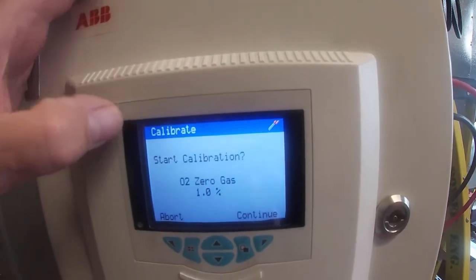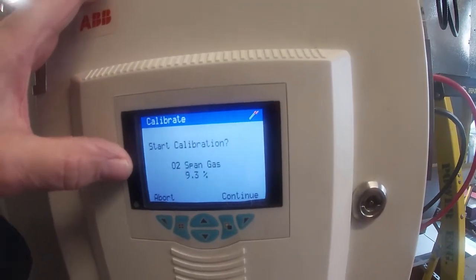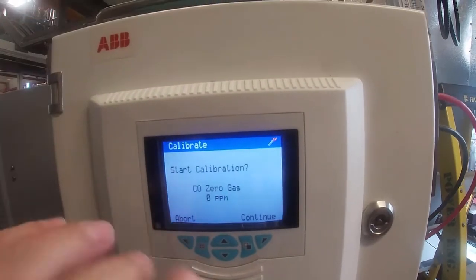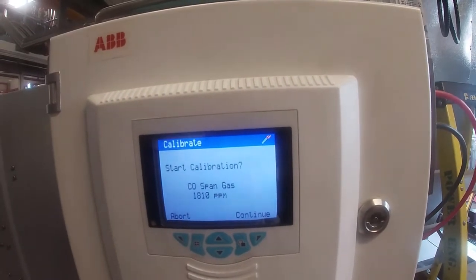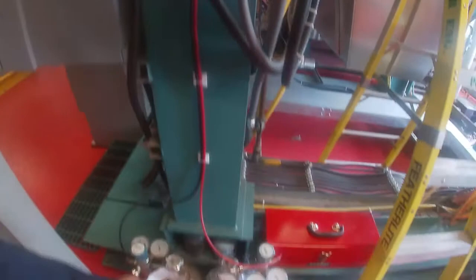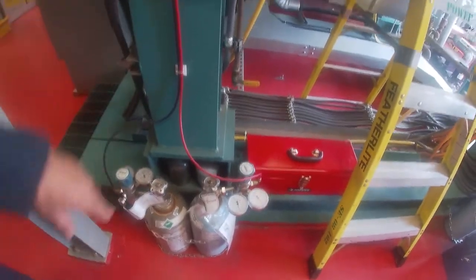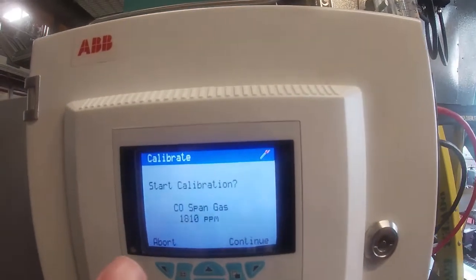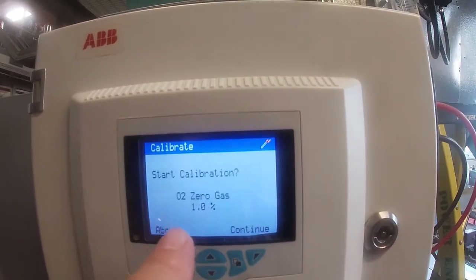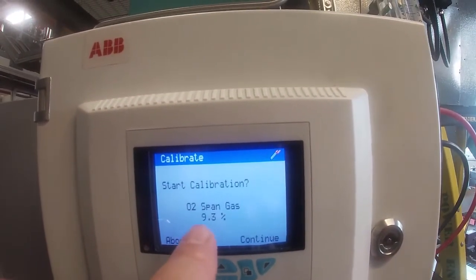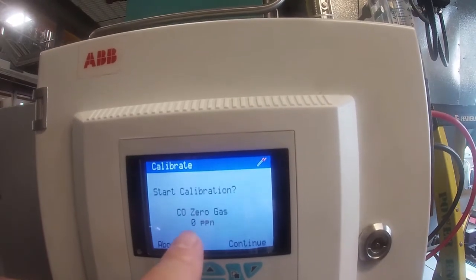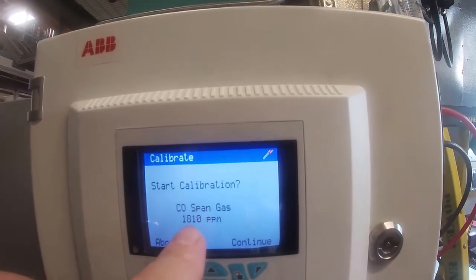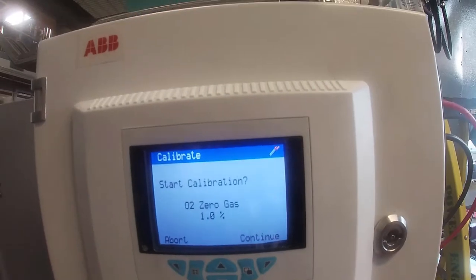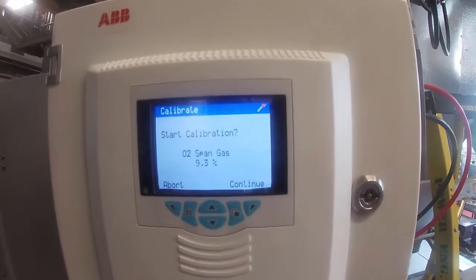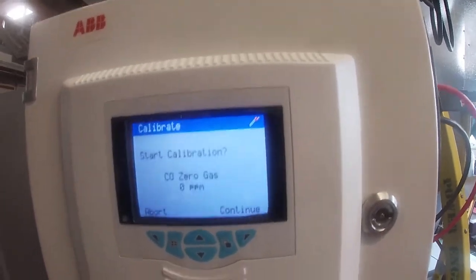Okay, so now I'm up to calibrate. It says, do I want to start the calibration? And I can abort or I can continue. You want to make sure that you've got the gas all set up, because this thing doesn't wait for anybody, and it'll get itself in a real knot if you don't have the gas. So it says I'm looking for 1% zero gas, 9.3% O2 span gas, 0 CO, and 1810 parts per million. So that's what it says it's getting for gas, and it's going to calibrate itself to that.